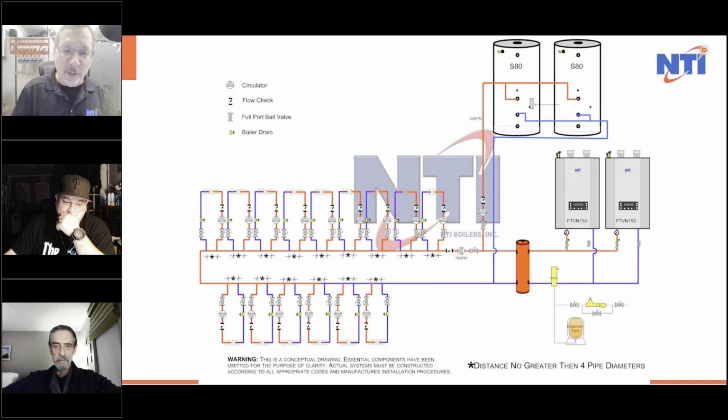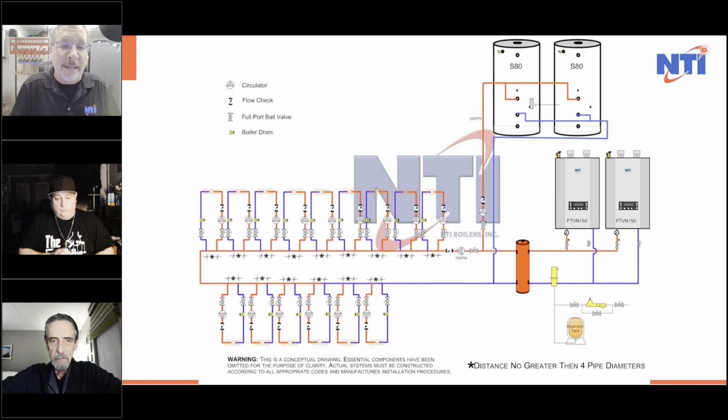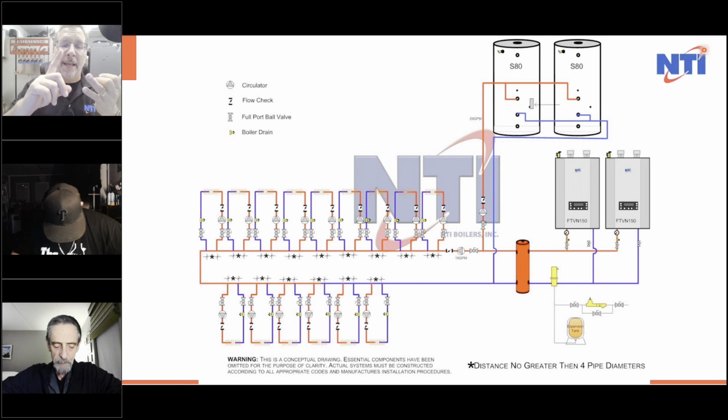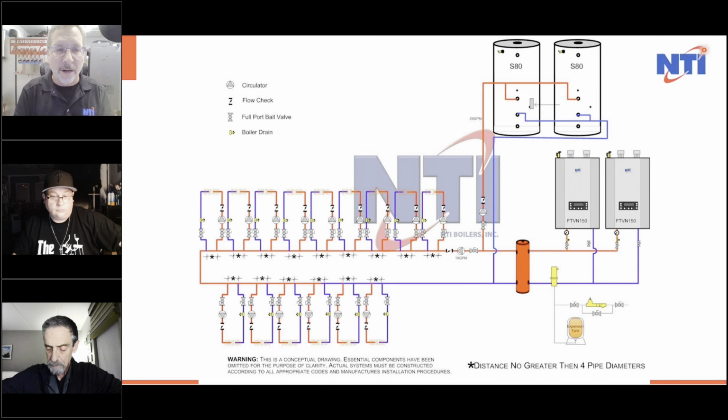We do the same in hydronics. We all ask what you want to get. We all ask what the flow rates are. I love when somebody calls me up and says, can you design this for me? And I say, what are your flow rates? And they go, I don't know. And I say, well, I can't help you. But if we know the flows, if we know the temperatures, if we know what the customer wants, if we know what you want, like redundancy and domestic hot water, we can design anything for you guys. And it will work no matter how it looks.